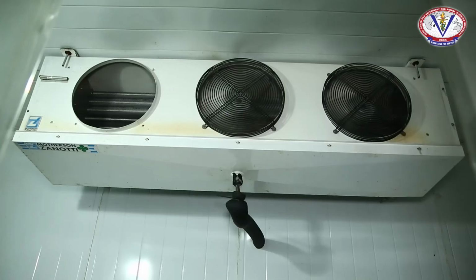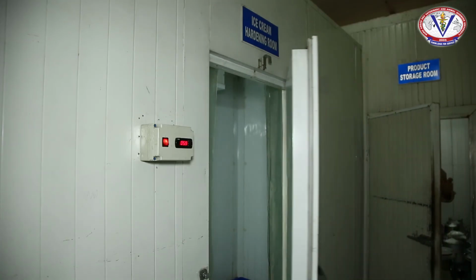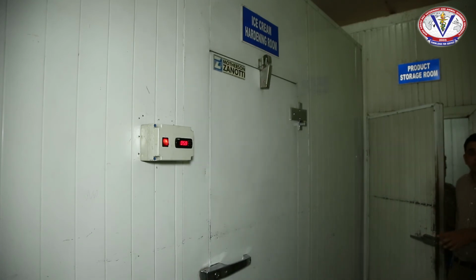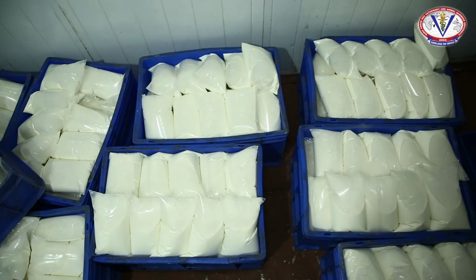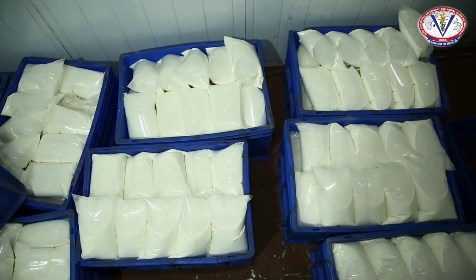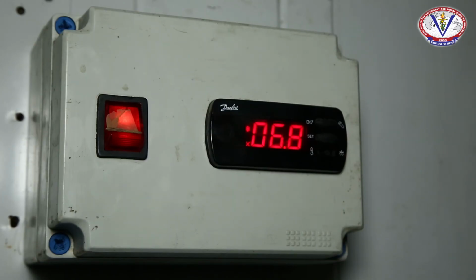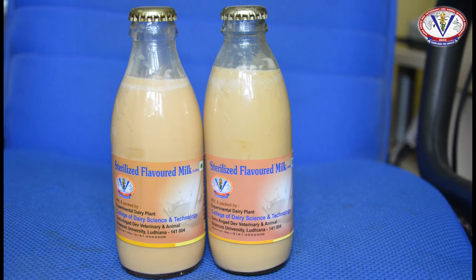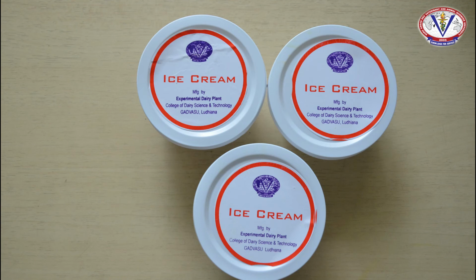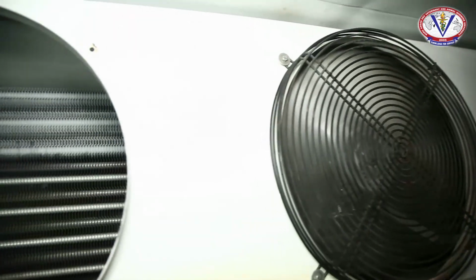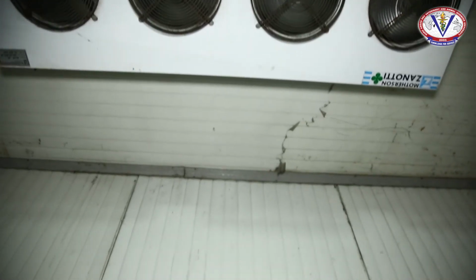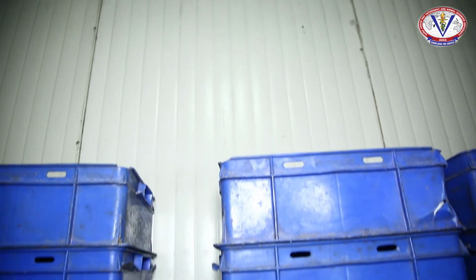Another application of these vapor compression refrigeration systems is where we are storing the product, that is the product storage or cold storage areas. Since the liquid milk is being stored at a temperature above zero, that is around 4 to 5 degrees centigrade, and the products such as ice cream or the butter have to be stored under sub-zero temperatures. So these vapor compression refrigeration systems are capable of achieving these two requirements in the milk plants.